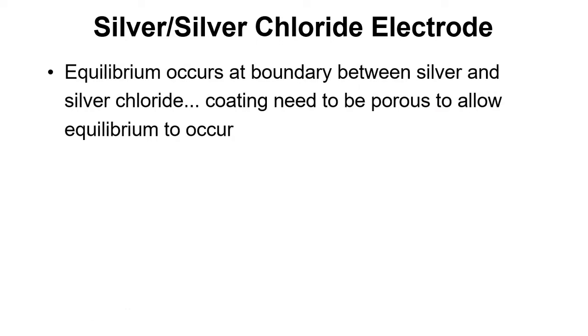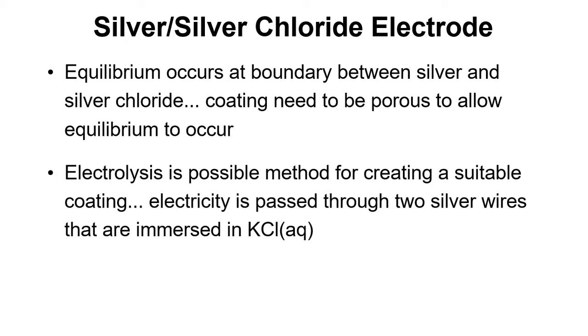The equilibrium occurs at the boundary between the silver and the silver chloride, so it's important that the coating is porous to allow this equilibrium to occur. It's possible to use electrolysis: if you put two silver wires into a KCl solution and pass electricity through one of those wires, you'll get a porous silver chloride coating.